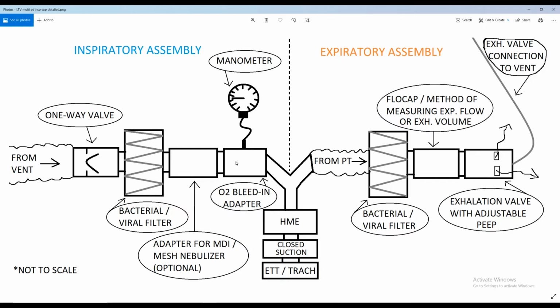You'd want to give a little bit of space, sort of like holding chamber type space right here leading to the Y connector. But you would definitely want it after the filter, obviously. And then how would we get our semi-accurate airway pressure measurement? I was thinking we could do this with just, we called it an O2 bleed-in adapter. Like, we'd use them for nocturnal CPAP setups and stuff. I don't officially know what that little adapter is called, but it's got the little 22 mm connectors. It will plumb right into a vent circuit, and it's got an outlet that you could potentially connect a manometer to. So any manometer that has the pressure range that you want to monitor.